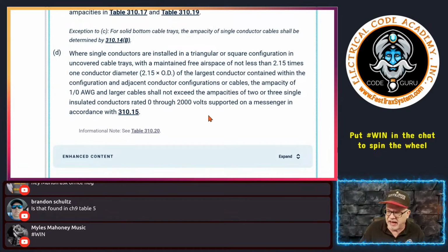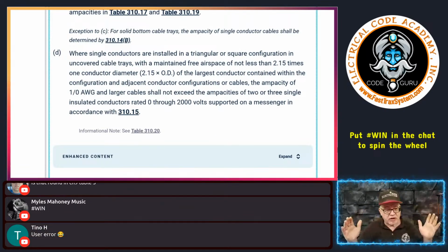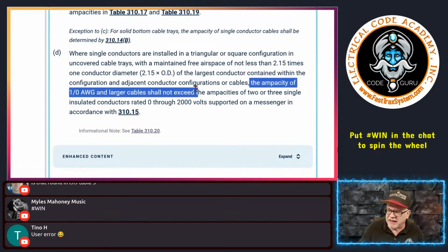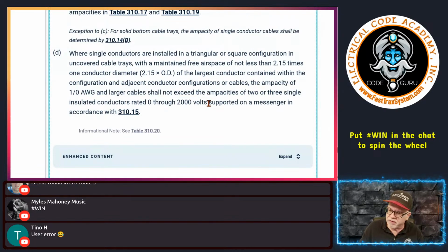I'll show you an example of that. Now, if that's the case, and you follow these rules in that tray, then here's what it says. The ampacity of 1/0 and larger cables shall not exceed the ampacities of 2 or 3 single insulated conductors rated 0 to 2000 volts supported on a messenger in accordance with 310.15. So why is that important?